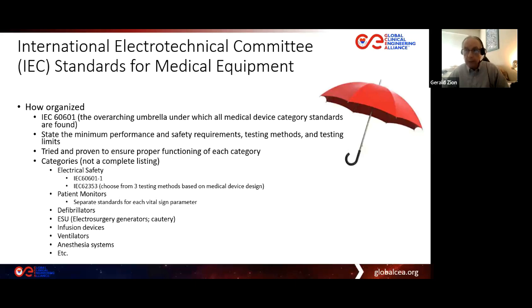So the listing here is not an exhaustive or complete listing, but it includes the 2 electrical safety standards that I just mentioned, and the patient monitors. In patient monitors, there is a separate standard for each vital sign parameter. And so be prepared for that. There's a separate one for ECG, separate one for non-invasive blood pressure, invasive blood pressure, and so forth. There's one for defibrillators, one for electrosurgery unit generators, electrocautery, separate one for infusion devices, for ventilators, for anesthesia systems, and so on. So underneath this umbrella, you will find the minimum performance and safety standards by medical device category for everything that we need to pretty much worry about.